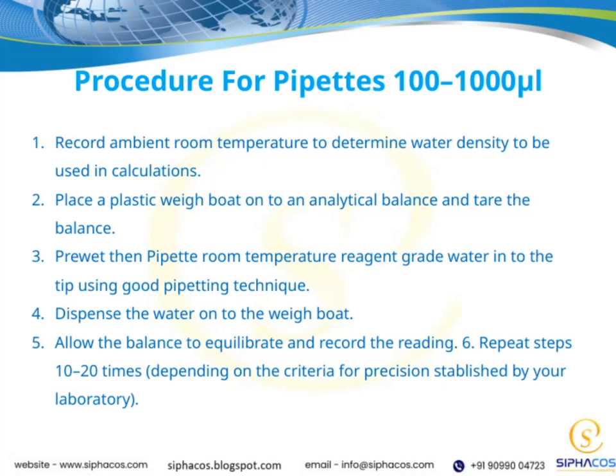Let's walk through the procedure for using pipettes in the 100 to 1000 microliter range. First, it's important to record the ambient room temperature. This helps us determine the water density, which is crucial for accurate calculations later on. Next, place a plastic weigh boat onto an analytical balance and tare it. That is, set the balance to 0 with the boat on it. This ensures we're only measuring the water's weight.